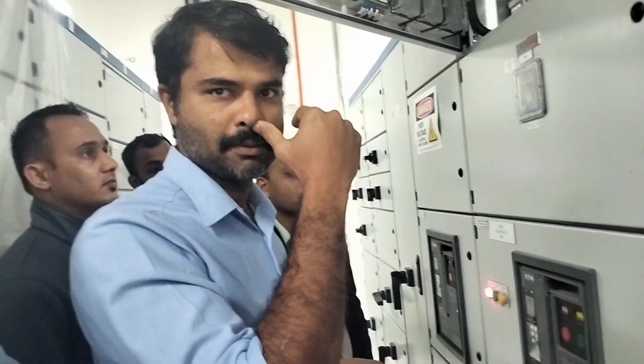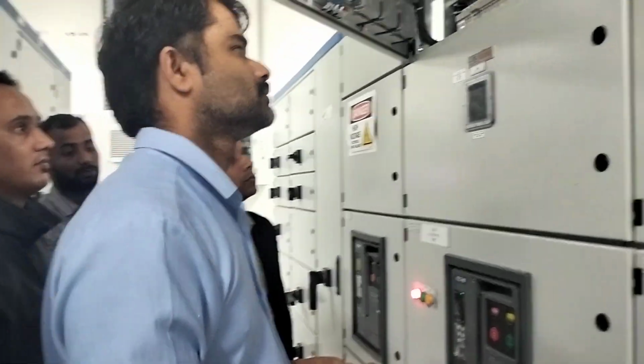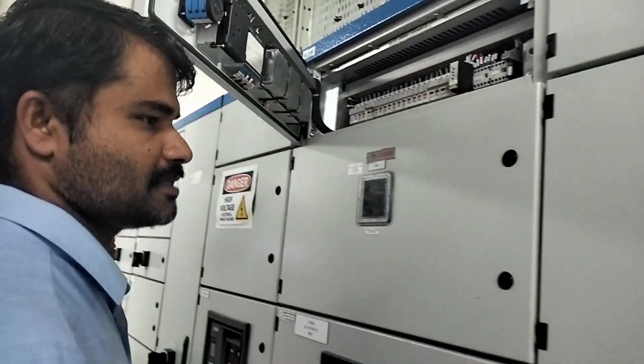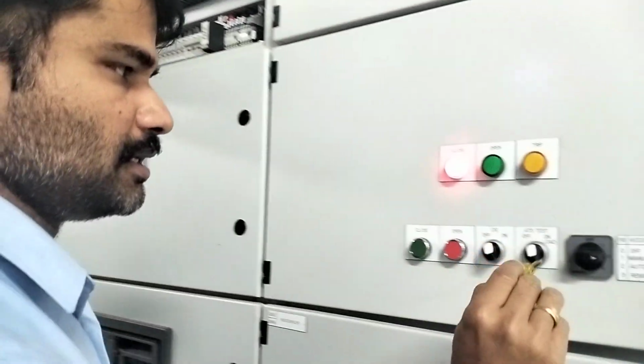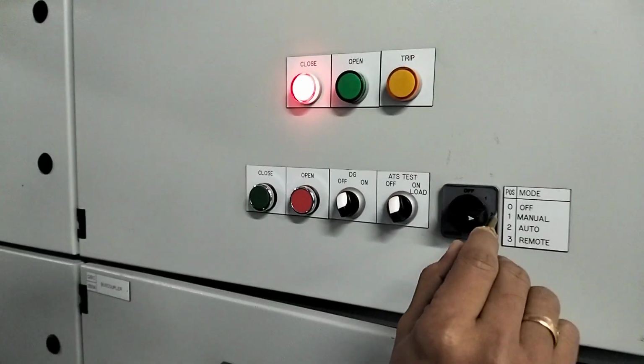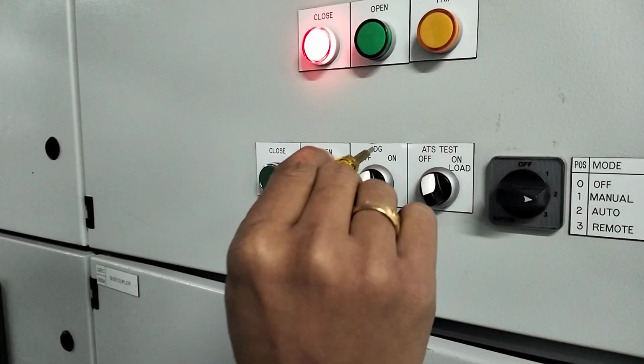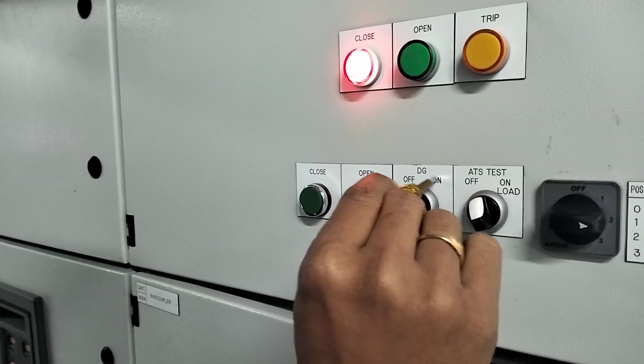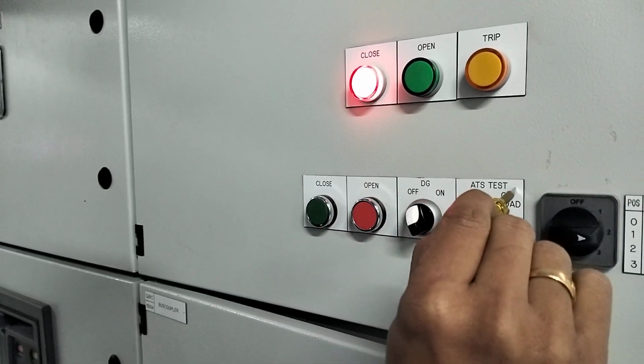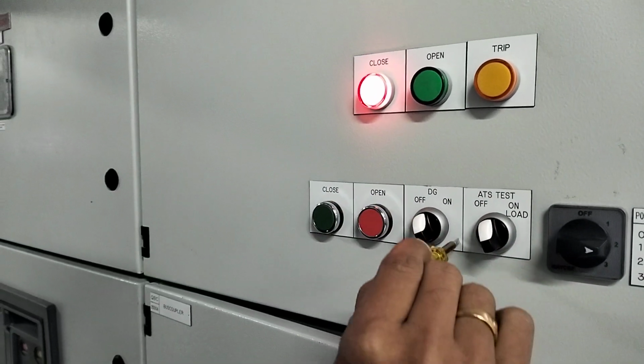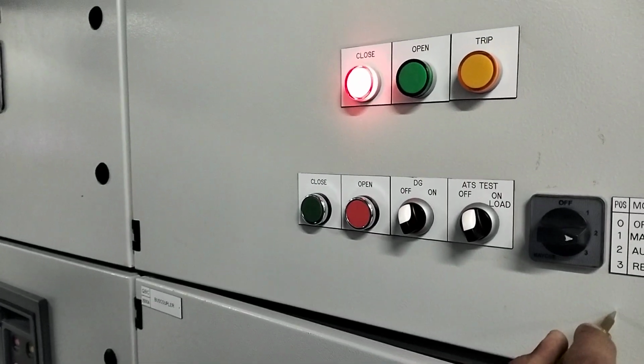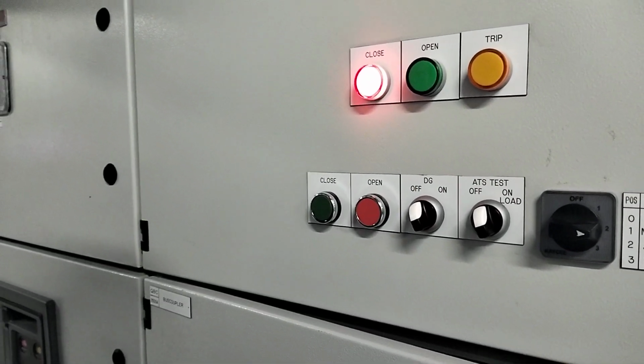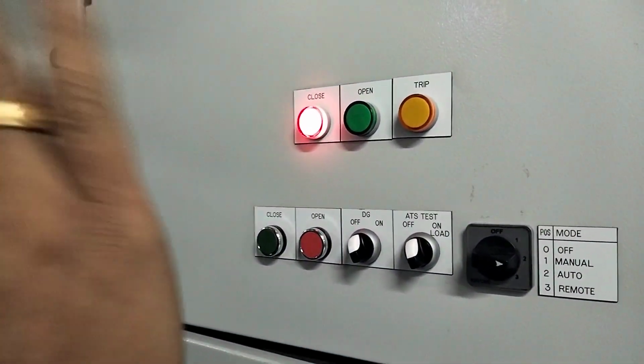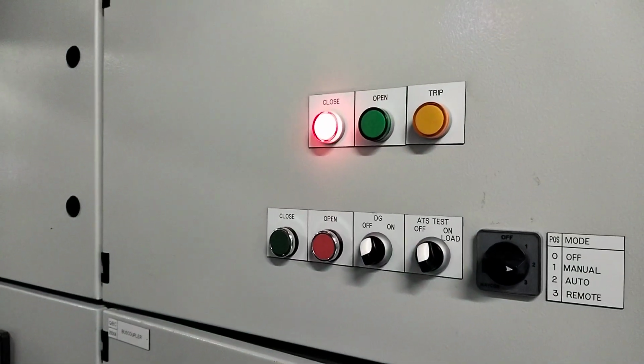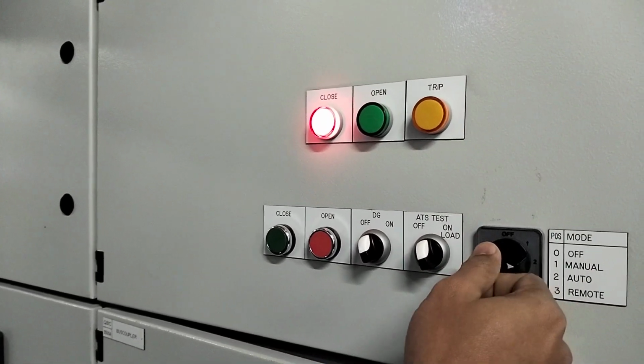Got it. Next, this is the switch. You have manual and auto. This is DG on and off. This is the ATS test. This function will work only when you are in manual. Let's say you want to do something. Your generator will always be in auto, correct? The generator will always be in auto. You are here, keeping your system in manual.